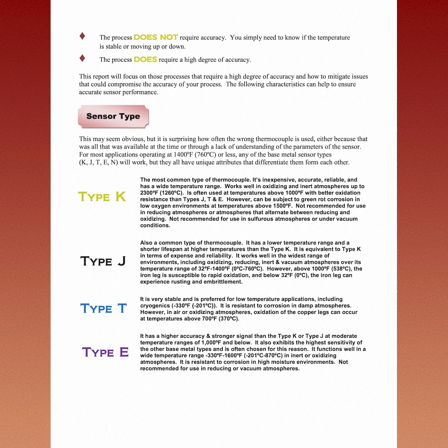Type J, also a common type of thermocouple. It has a lower temperature range and a shorter lifespan at higher temperatures than the Type K. It is equivalent to Type K in terms of expense and reliability. It works well in the widest range of environments, including oxidizing, reducing, inert, and vacuum atmospheres over its temperature range of 32 to 1400 degrees Fahrenheit or 0 to 760 degrees Celsius. However, above 1000 degrees Fahrenheit or 538 degrees Celsius, the iron leg is susceptible to rapid oxidation, and below 32 degrees Fahrenheit or 0 degrees Celsius, the iron leg can experience rusting and embrittlement.